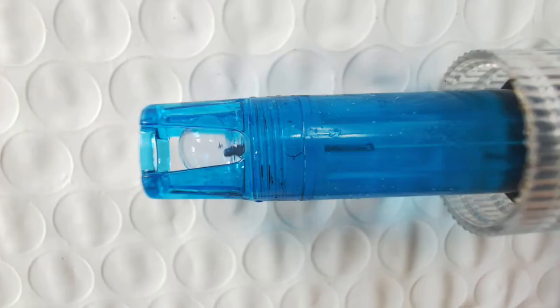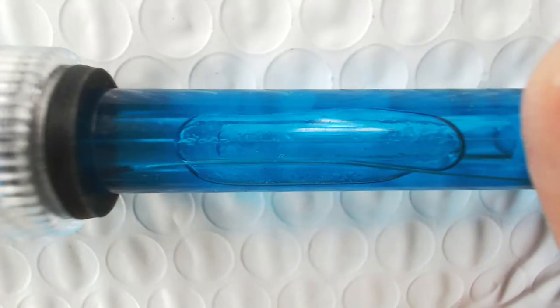Okay, let's get into a few more details. In my case, you have a plastic overbody, and the probe itself is made out of glass. The glass is a very special glass. It's electrically conductive. The bulb on the inside is hollow. There's a sensor wire on the inside of it, as well as an interior fluid. Nothing should touch the glass part of the probe except what is actually being measured by the probe. This particular probe is designed to be installed vertical down. As you can see, there is an air bubble inside the probe.